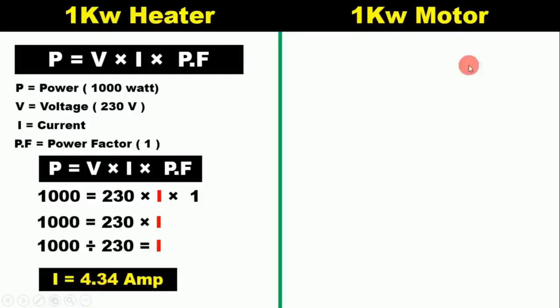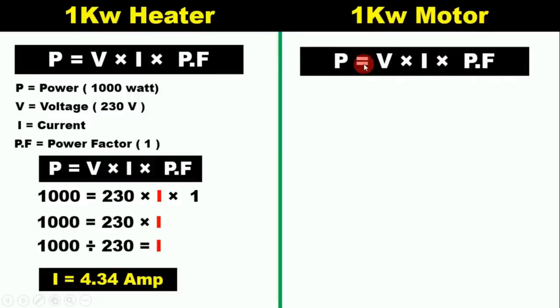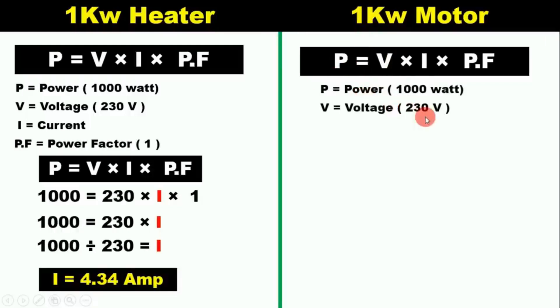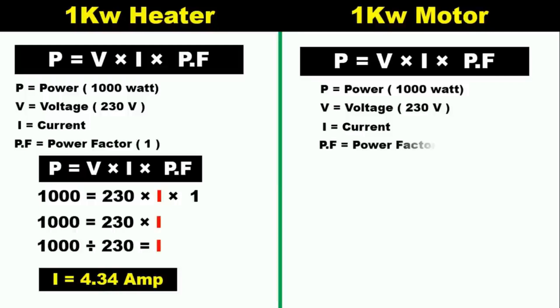Now we have to find the current value for the motor. The motor of 1 kilowatt here is also single phase, so we use the same formula: P equals V into I into PF. Power is 1000 watts, voltage is 230 volts. Now what is the power factor? The motor is an inductive load, and the power factor of an inductive load can never be 1 — it will always be less than 1. If the power factor is not given, you can consider it as 0.8. So we take power factor as 0.8.